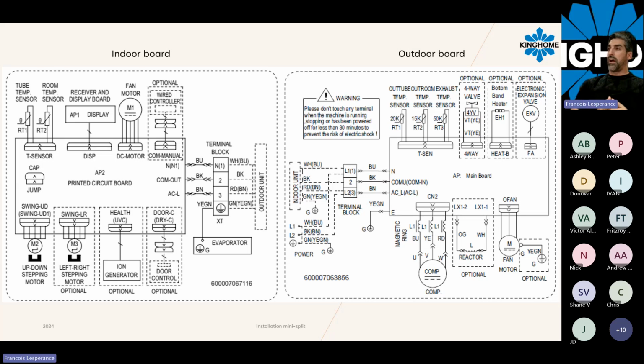We can take a look at an example here of those boards. So I have a picture of the outdoor board and a picture of the indoor board. Just to show you guys, when you look at this schematic, where is located the sensor. So for example, if you have F1, F2, F3, F4, F5 error code, they are related to sensor. So if one sensor goes bad because it's open, the wire has been cut, or it's out of range, well, when you will order that part, you can see here they come all three together. So we will have to change all three sensors.